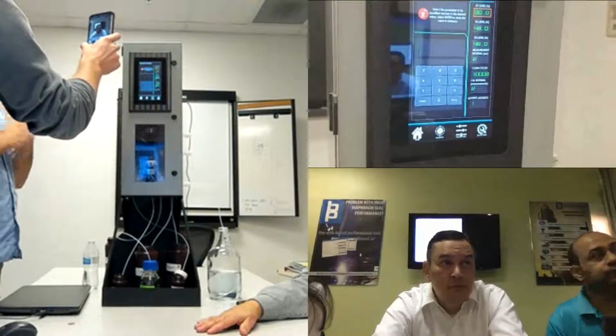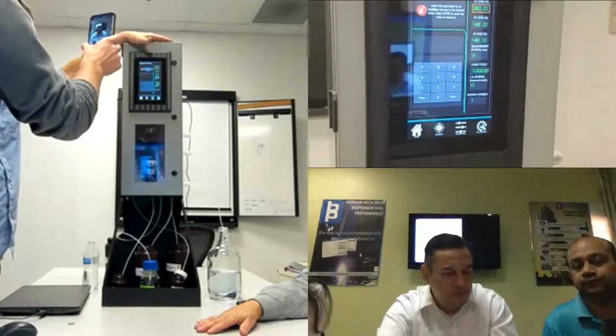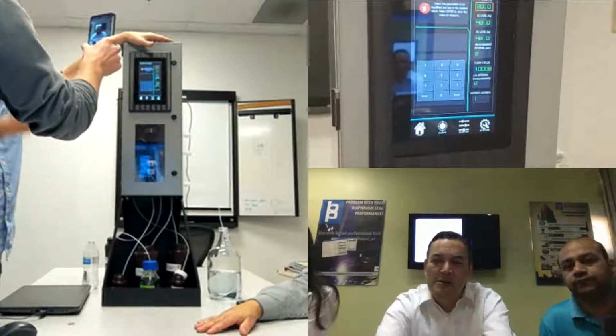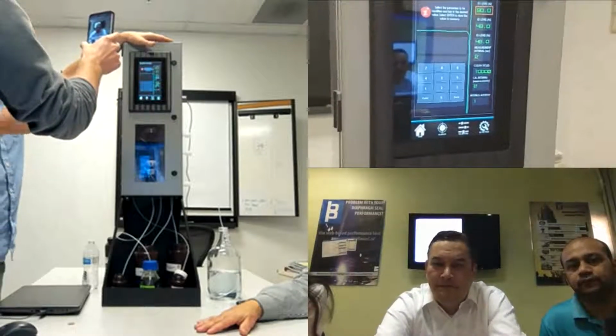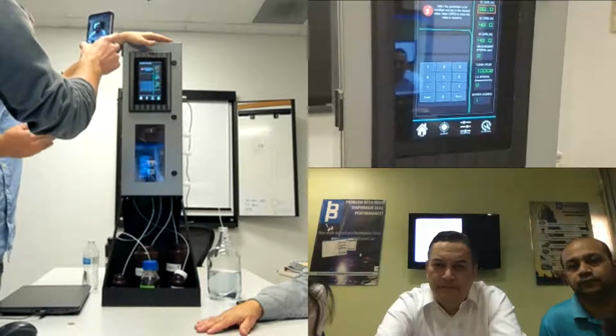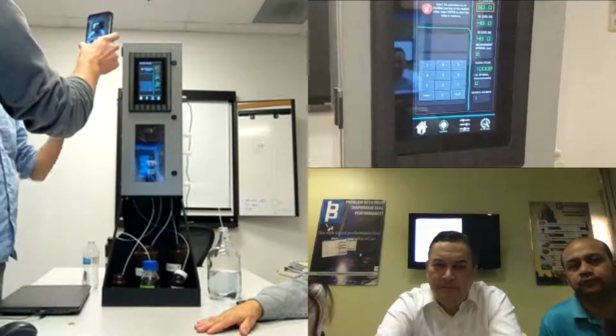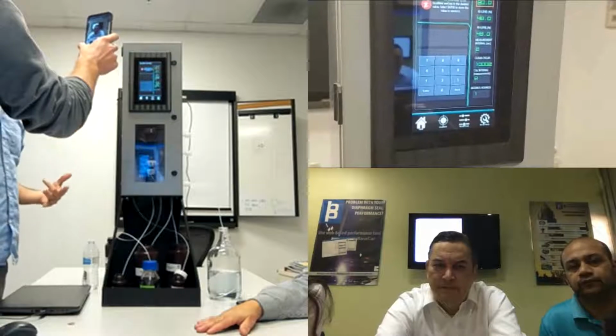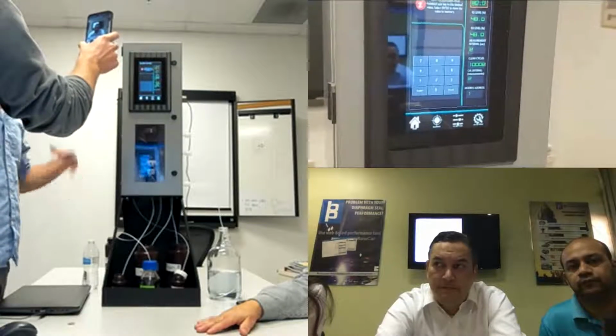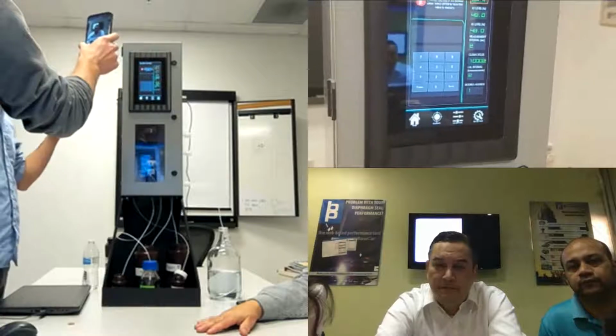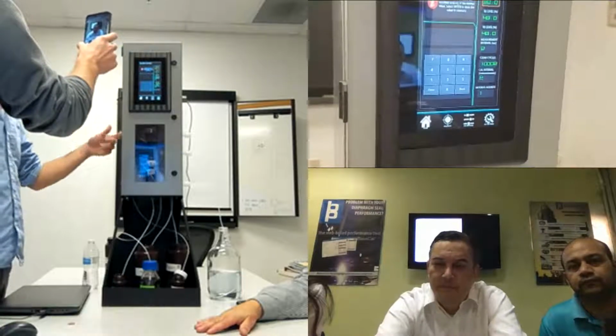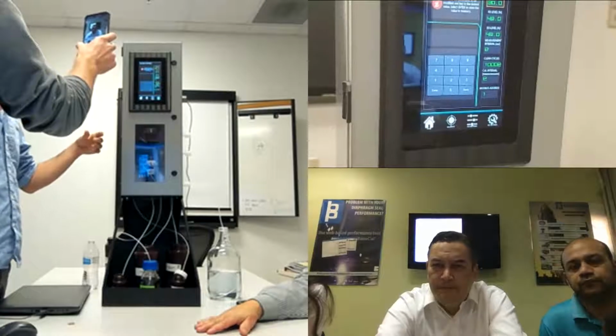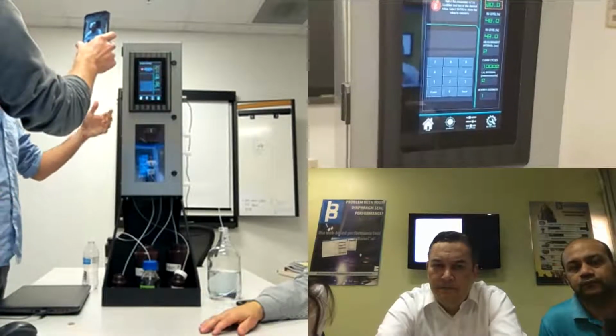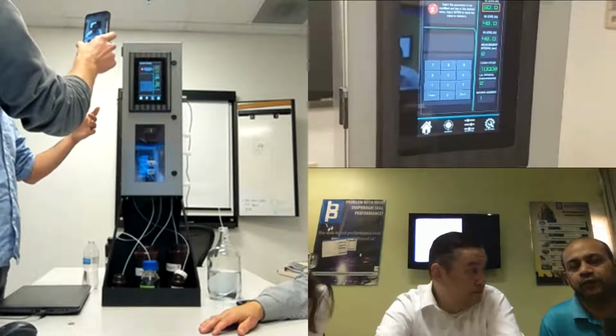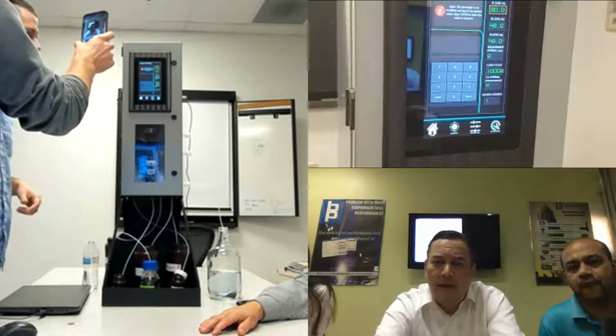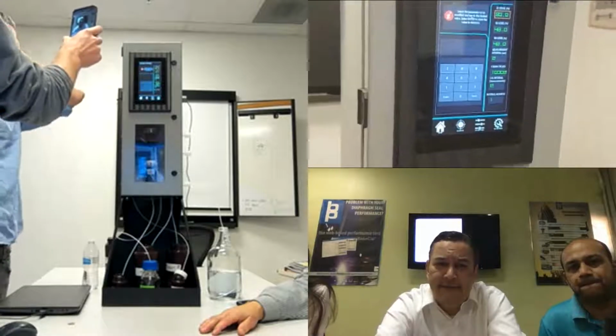We actually monitor the reagent levels. Every time you make a measurement or pull a reagent, we automatically decrement the volume that's used. After a series of measurements, the software will warn you when the reagents are getting low. It will set off an alarm, letting you know via the display, Modbus, and an alarm relay on the back of the unit, so that'll let you know when it's time to replace your reagents.